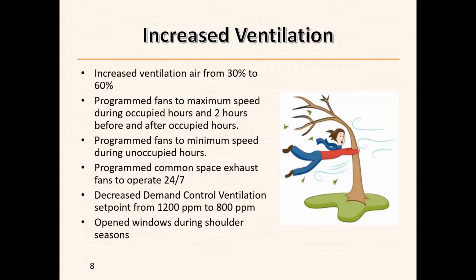To augment that, we programmed the exhaust fans in common spaces to operate 24/7, which increases the overall air coming in throughout the building. We also programmed any systems that modulate ventilation air, so outside air, based on the space's carbon dioxide levels, which is a measurement of occupancy, to operate with more ventilation by decreasing the set point of that control from 1,200 parts per million to 800 parts per million. This basically ensures that when there is occupancy of any kind, the air handling unit's outside air dampers will open up.